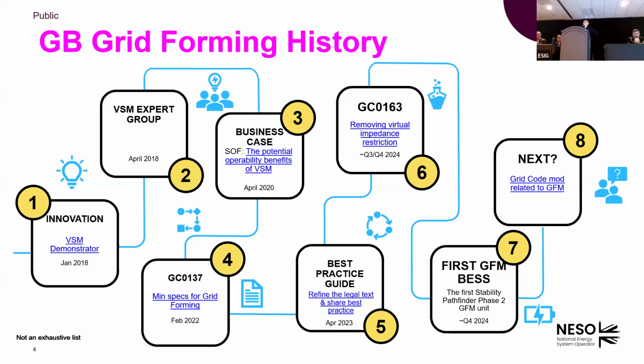And we were thinking, what's the best way to solve that problem? Traditionally, we ran the system with 100% synchronous machines for many, many years, and there seemed to be no issues with that. So if the IBR can behave like a synchronous machine, whether that problem can be solved. That's the reason we kicked off research projects looking at whether the IBR can behave like a synchronous machine. We did quite a few research projects, and also some demonstrations, to see if we can change the control system of the IBR so it could behave like a synchronous machine, then we can keep on increasing the IBR penetration level.